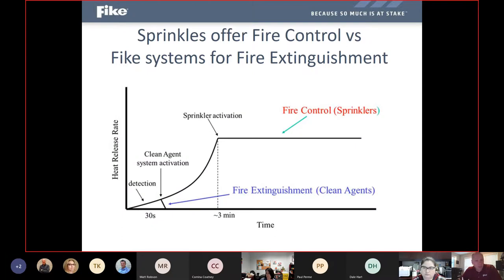The other byproduct or disadvantage of sprinkler systems is they're going to be the last one to act when there is a fire. So if you look at time there on the horizontal axis, you're going to have a significant amount of time that develops by the time a fire has started, even from a smoldering condition, till it releases enough heat to actually activate a sprinkler system. It could be several minutes.